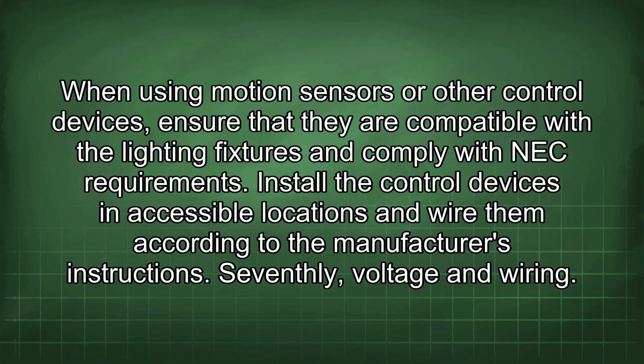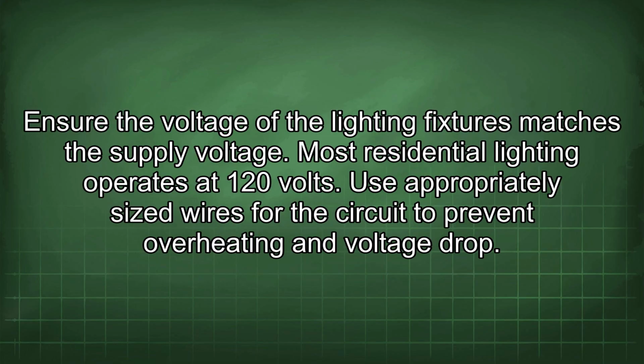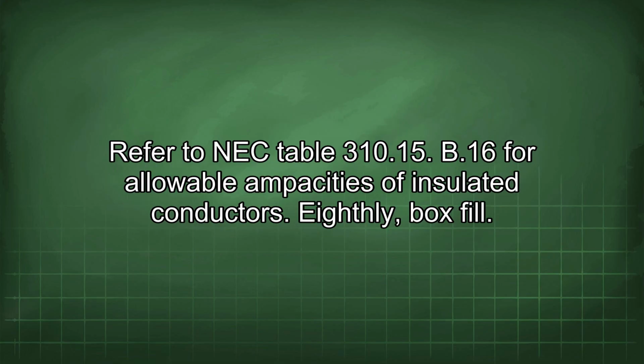Seventhly, voltage and wiring. Ensure the voltage of the lighting fixtures matches the supply voltage. Most residential lighting operates at 120 volts. Use appropriately sized wires for the circuit to prevent overheating and voltage drop. Refer to NEC Table 310.15(B)(16) for allowable ampacities of insulated conductors.